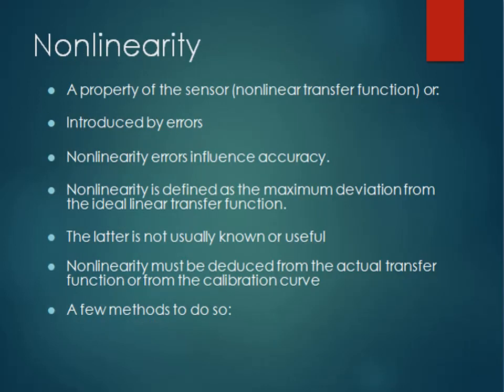Now we'll talk about nonlinearity, a property of the sensor introduced by the errors. So nonlinearity errors definitely influence the accuracy. Nonlinearity is defined as the maximum deviation from the ideal linear transfer function, and the latter is not usually known or useful. So nonlinearity must be deduced from the actual transfer function or from the calibration curve.